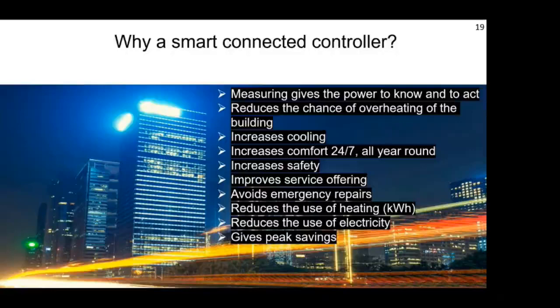Smart connected controllers can be configured to raise alarms on changes to the substations, giving improved safety. It could be temperatures dropping inside, outside, flow and return. There could be lots of things set up. Remote access can also give an improved service offering to the stakeholders, saving time, money and energy whilst minimising the impact on their clients. If the heating went off in a commercial building, how quick would people notice? In the summer, they wouldn't notice at all. In the winter, they would possibly notice, but it'd maybe only be an hour or two. But if someone is monitoring the heat substation via the controller, they know straight away that an alarm is being sent, that the system's gone down or isn't performing. So straight away, someone's on the case.